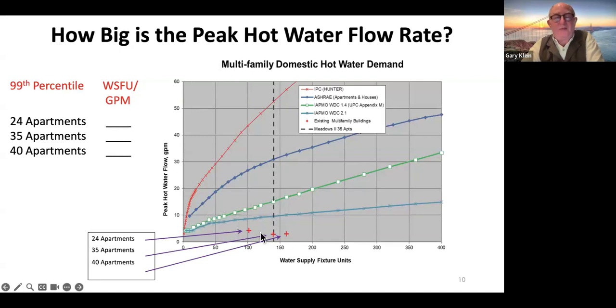Here are the three measured data points for the 24, 35, and 40-unit apartment building. Here's what the plumbing code predicts for the 35-unit apartment building for the project we were on. This is what the ASHRAE modified method predicts. This was version one of the water demand calculator, which was all we had available at the time, Christoph. And version two came out after the project had already been built.